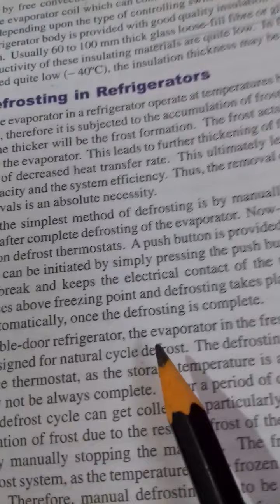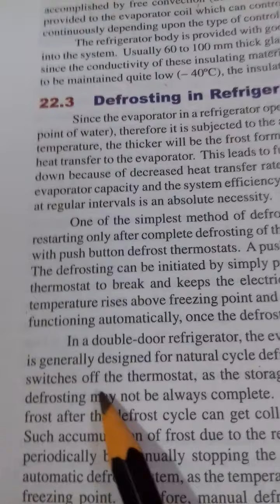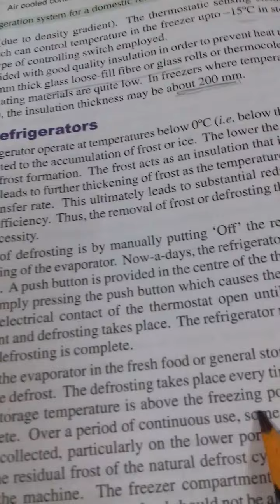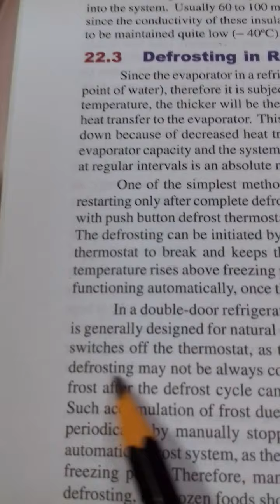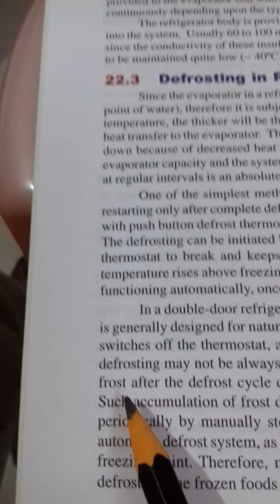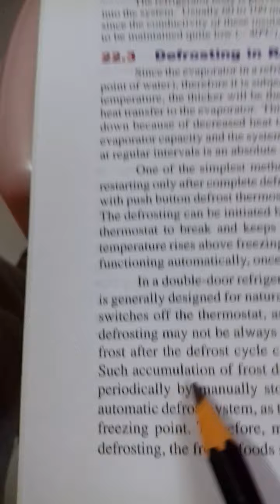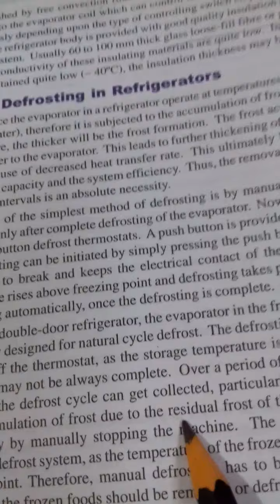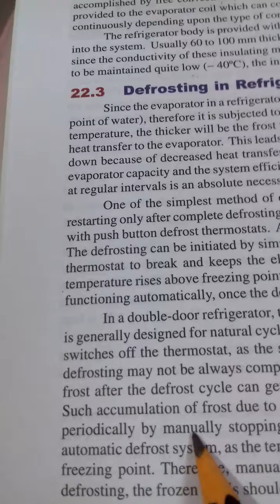Next, in a double door refrigerator, the evaporator in the fresh food or general storage compartment is generally designed for natural cycle defrost. The defrosting takes place every time the compressor switches off by the thermostat, as the storage temperature is above the freezing point. However, the defrosting may not always be complete. Over a period of continuous use, some amount of residual frost after the defrost cycle can get collected, particularly on the lower portion of the evaporator. Such accumulation of frost due to the residual frost of the natural defrost cycle has to be removed periodically by manually stopping the machine.